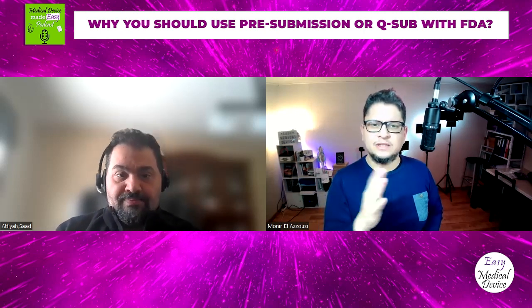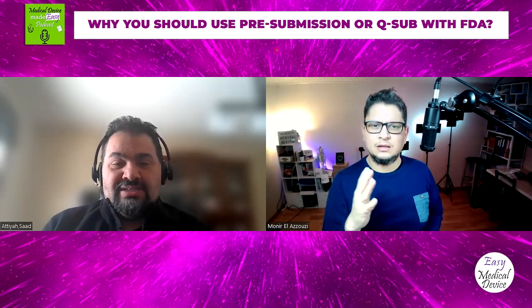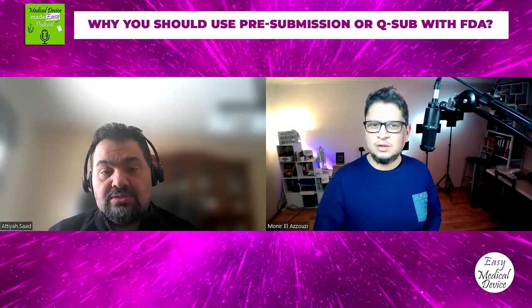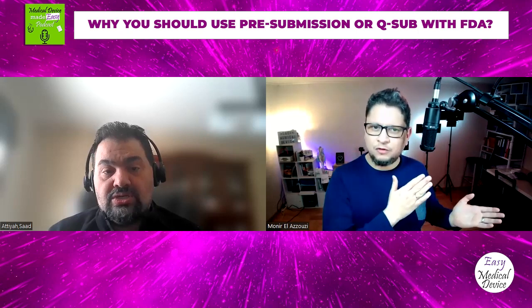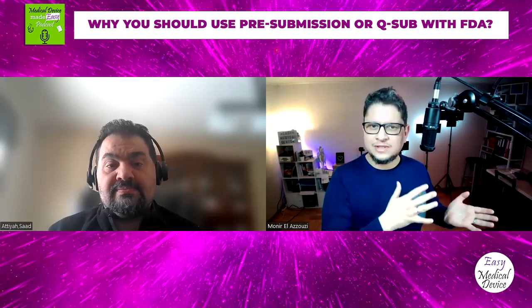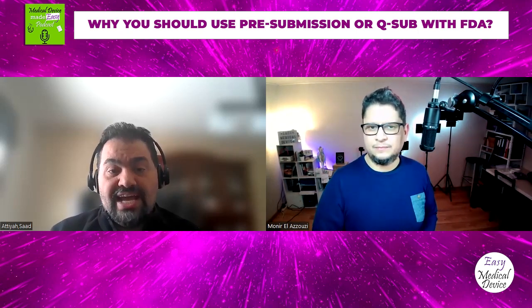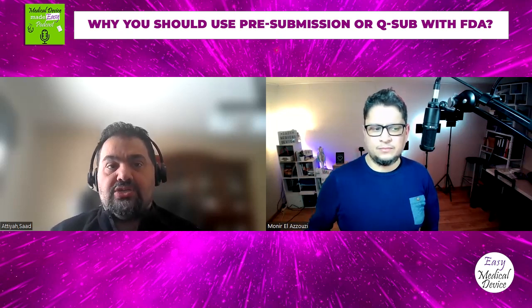And the 70 to 90 days mainly has to be also placed in your calendar, because it can be a long time. So if you think that you are ready for submitting, but you want a pre-sub before, then you have like 3 months to wait before maybe receiving an answer about that. So it's really something that they have to take into account if they want really to go there. It's why asking for it really early in the process is really key here. Planning is essential. Planning is essential.